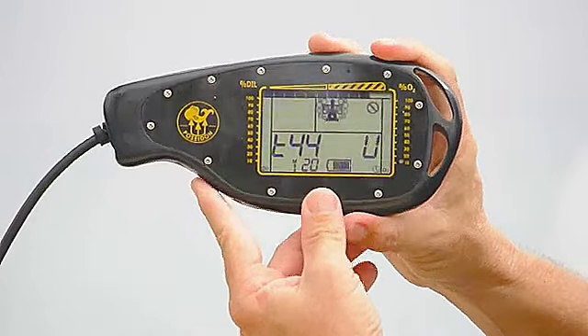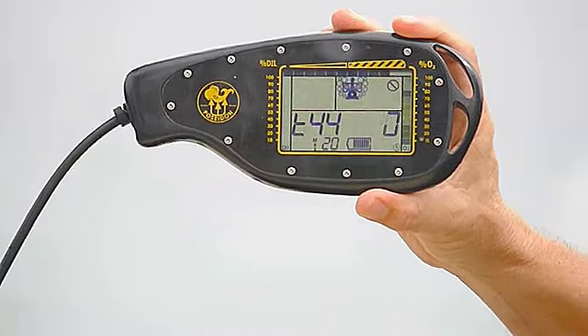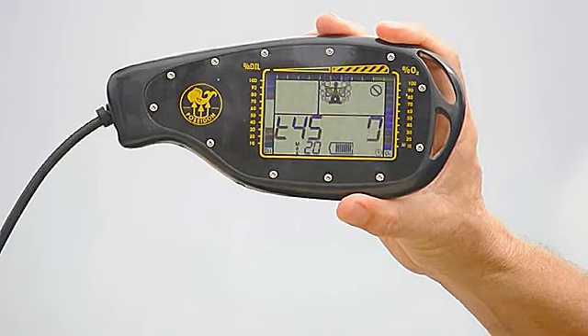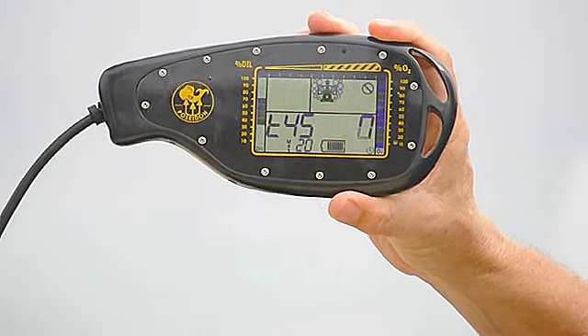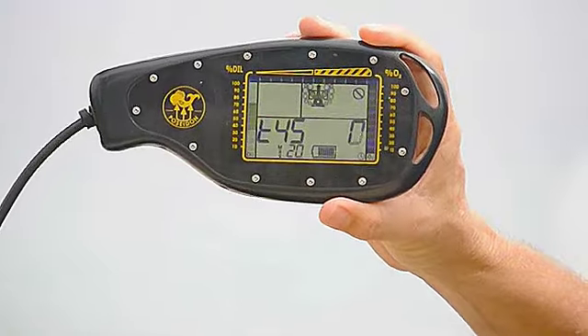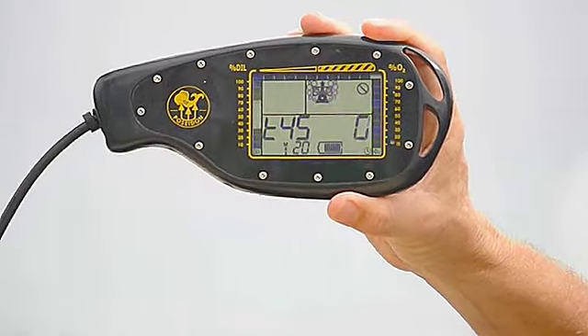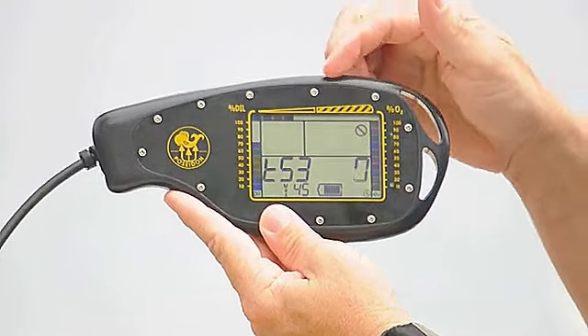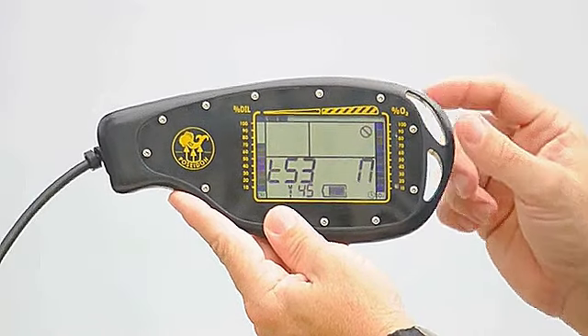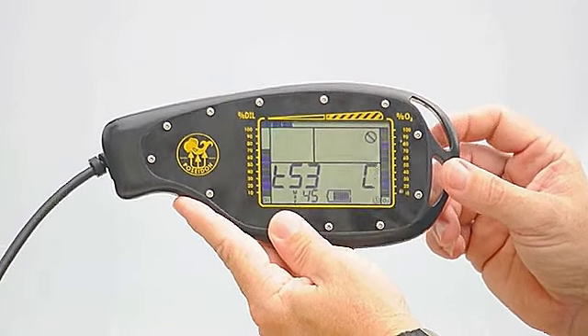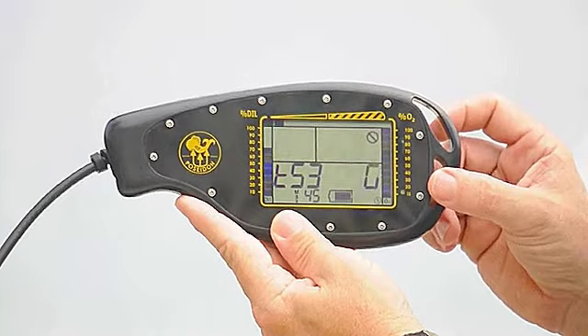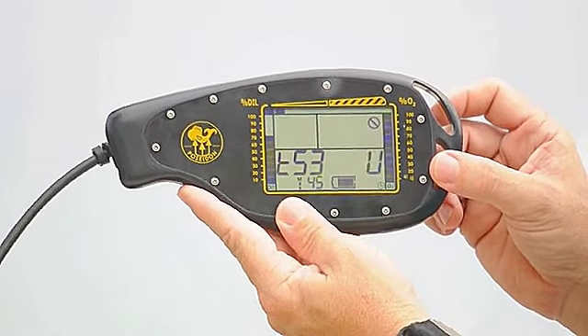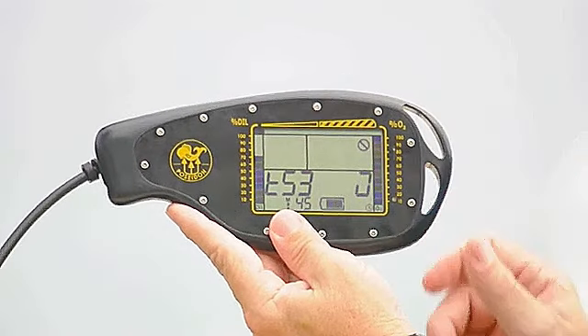Also, that test is important because it verifies that the oxygen solenoids and the diluent solenoids are actually injecting gas. So if you've left your cylinder off or if there's a blockage in the regulator, it will fail that test. Because in addition to all the other tests it runs, it also does the oxygen sensor calibration and makes sure that both oxygen sensors fall within the right calibration range. And it does a couple of other tests after that.